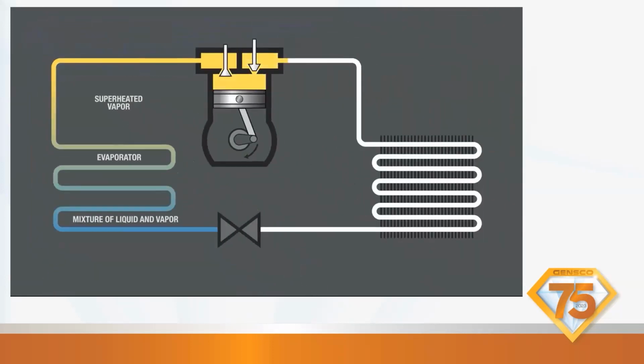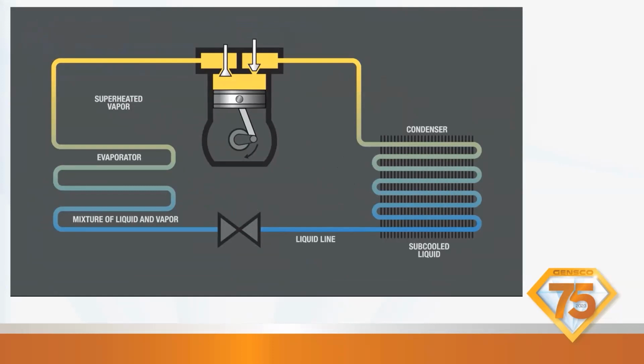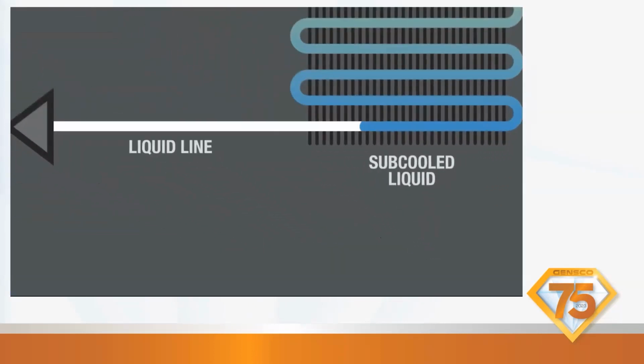Now let's look at subcooling. As refrigerant enters the system's condenser, it's in a vapor state. As heat is removed from the vapor, it will turn to liquid at its saturation condensing temperature. After the vapor has turned to liquid, any temperature of the liquid below this saturation condensing temperature is called subcooling. Because the efficiency of the system is optimized with subcooling, you want to make sure that you have a constant supply of liquid to the evaporator. So it's important that the refrigerant is subcooled to prevent it from turning to gas before it gets there. A smaller amount of refrigerant is required to maintain the desired temperature, which means less work for the compressor.